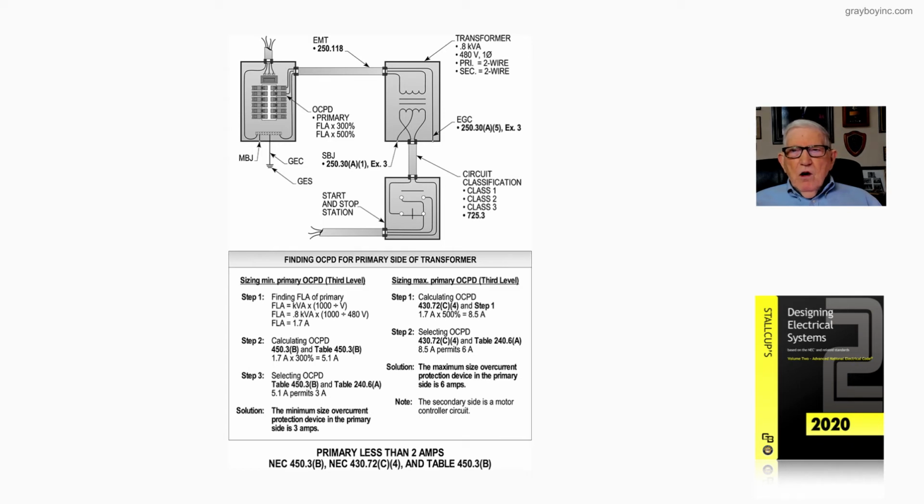So we know then that it's either a Class 1, 2, or 3 that we'd be using, and in the range that we see there, more than likely we're going to be dealing with a Class 2 or Class 3 circuit. But we've given you those sections. A Class 1 circuit, you can get those outputs in 725.41(A) for a power limited circuit, and that's 1,000 volt-amps or less, and we'd be at 30 volts or less.